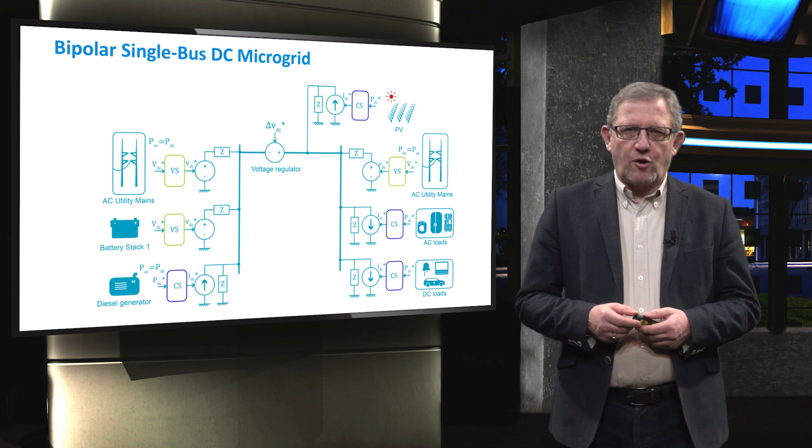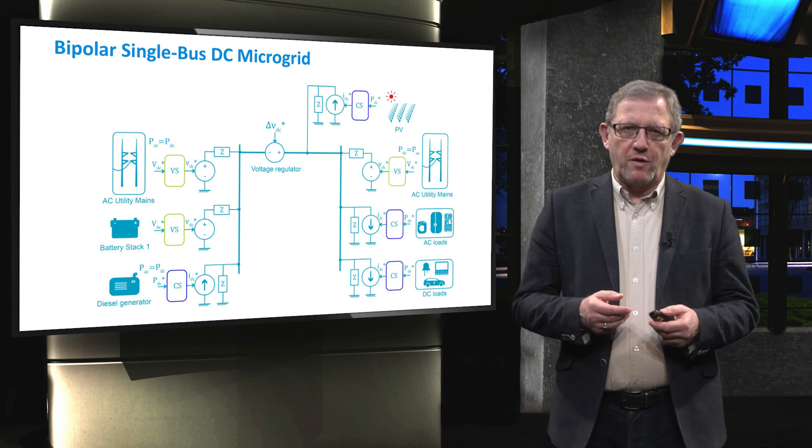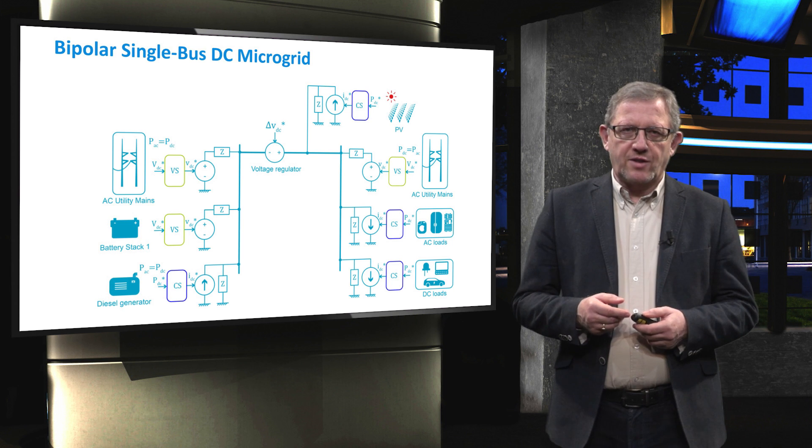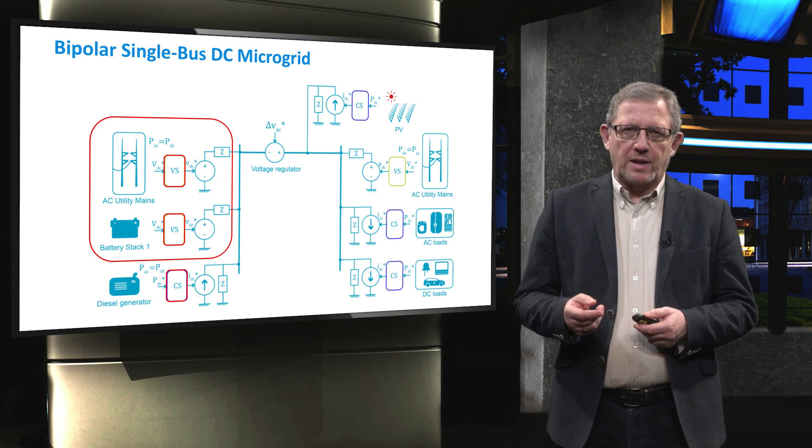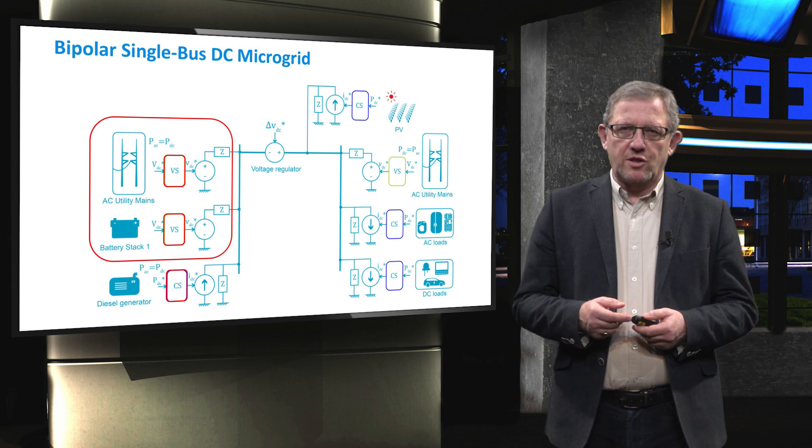In this slide we can see the grid forming and grid feeding representation of the DC microgrid. At the monopolar single bus on the left side, both AC grids — the AC utility mains and battery stack — are able to control the DC link voltage. If the grid is strong, it is typically the best choice to control the monopolar DC link voltage. However, if the grid is weak, the battery bank or diesel gas generator can be used to regulate the monopolar DC voltage. At the bipolar DC link on the right, PV solar units, AC loads, and DC loads are all represented by grid feeding or current source with parallel impedances. The bipolar DC link can be controlled by the AC grid on the right or by the monopolar DC link on the left.